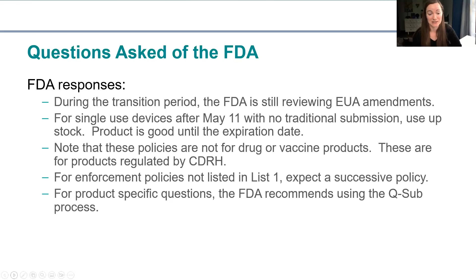For those, just as Jianlin said, please remember about the availability of the Q-Sub process. In this process, you can submit a specific question to the FDA and the FDA will respond. An example of the type of question would be whether a manufacturer who does not intend to continue distribution can replace or repair ventilators which malfunction. This would be a great candidate for a Q-Sub because the FDA's response will differ depending on the type of repair or modification necessary. So I hope you found this webinar helpful.